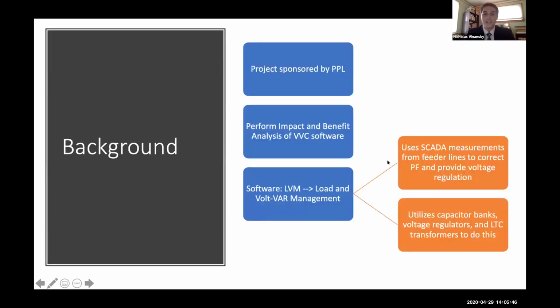My project is sponsored by PPL, specifically their distribution operations team. My goal is to perform an impact and benefit analysis of the Volt-VAR control software, determining how PPL benefits operationally and financially from its use. The software is called Load and Volt-VAR Management, or LVM. SCADA measurements from feeder lines are used to correct power factor and provide voltage regulation throughout the distribution network, using three major devices: capacitor banks, voltage regulators, and load tap change transformers.